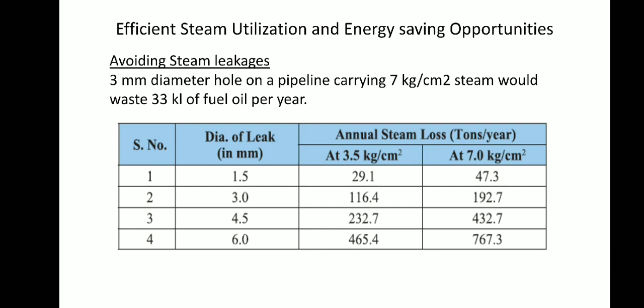And the table presented the significance of losses through steam leaks. For example, a 3 mm diameter steam leak hole in the pipeline leads to a loss of 116.4 tons of steam per year at 3.5 kg/cm², and 192.7 tons of steam per year at 7 kg/cm². This is the loss due to steam leakage. This must be avoidable.